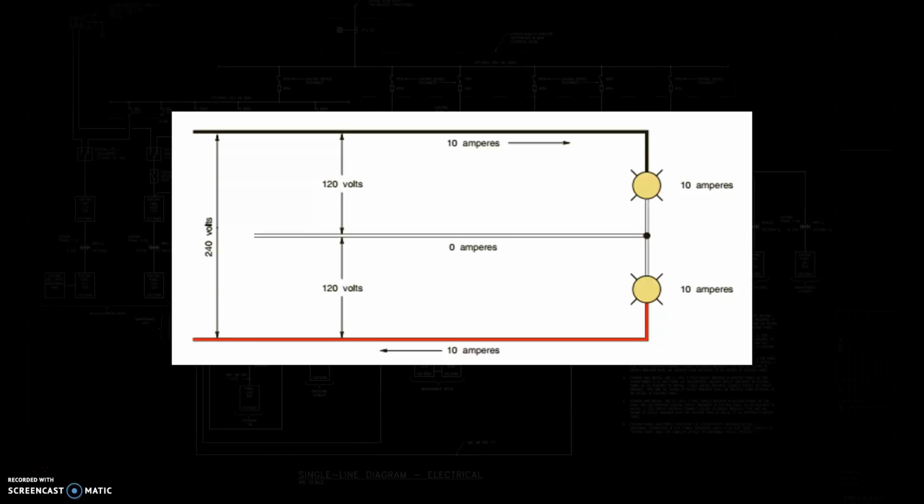If we have two circuits, okay, maybe they're at the same place. So think of your small appliance branch circuit in a kitchen. You need two circuits in a relatively close space. Maybe you're just going to run one 3-wire. You have a black, which is one hot. You're going to have a red, which is another hot. And then let's share our neutral between the two. Now you can do that, and there's certain things you need to follow and ways you have to do that.